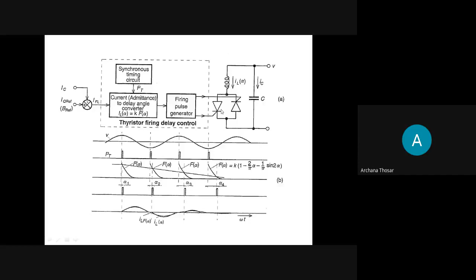You can see the reference is IC and the IQ reference. This gives current to the admittance block, which converts it into the delay angle. This way you have to establish a control system, which is very important, because functionally you understand it, but you need to trigger or fire these devices at the correct instances and with the correct frequency.